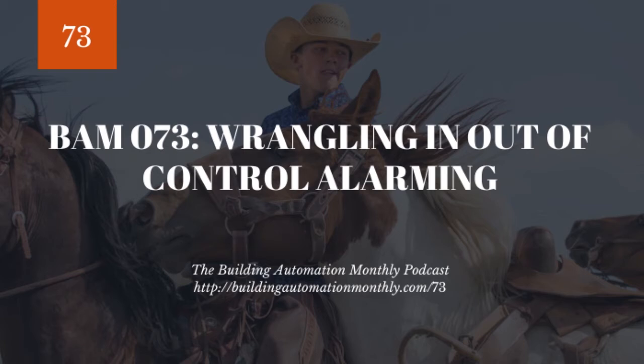Well anyways, all the alarms were exactly the same priority. And because of this, these critical alarms - things that could literally take down the entire campus - were being intermixed with things like filter alarms and condensate drip pan alarms. And it was like, wow.